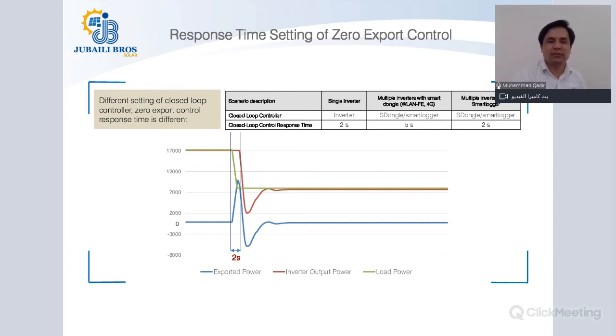Response time setting of zero export control. By default, the inverter closed loop control is around 2 seconds, because as soon as the power sensor reads the data on the grid side that there is some extra generation going towards the grid, the time till the inverter responds to that power excess going towards the grid takes around 2 seconds. So in case of a smart dongle, as described earlier, it's around 5 seconds, and again, in case of the smart logger, it's around 2 seconds.